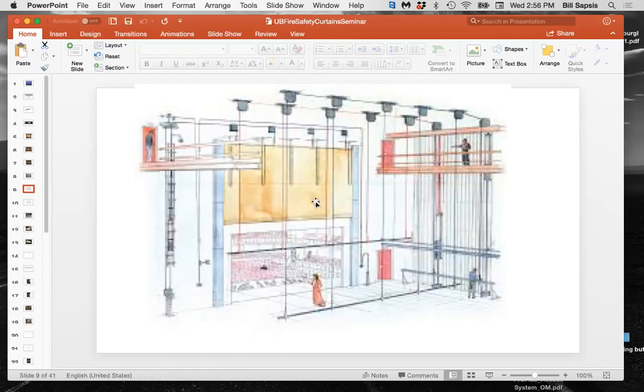We don't balance for that. We balance 500 pounds for the curtain, so we put 500 pounds here. We don't counterbalance for the, let's say 50 to 75 pounds worth of chain weight that is hanging from the top of the curtain down to the bottom of the loop. So when you trip the emergency release line, the curtain's out of weight and it's going to want to come down. And as it comes down, it's going to start off pretty good because you're out of balance by about 75 pounds or somewhere in that neighborhood. It's going to start coming down pretty good.